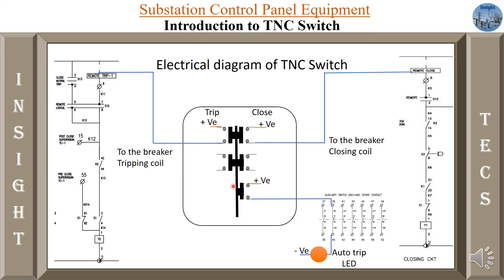Whenever you move the TNC switch towards the closed side, the auto-reclose contact becomes NC. Since the circuit breaker is not actually closed, the auxiliary switch remains closed as well. This means positive supply reaches the auto trip LED, causing it to glow on the panel. That LED indicates: although you have closed the switch from the control panel, the breaker in the switchyard is still open. This is a warning indication that there is some issue in the closing circuit.